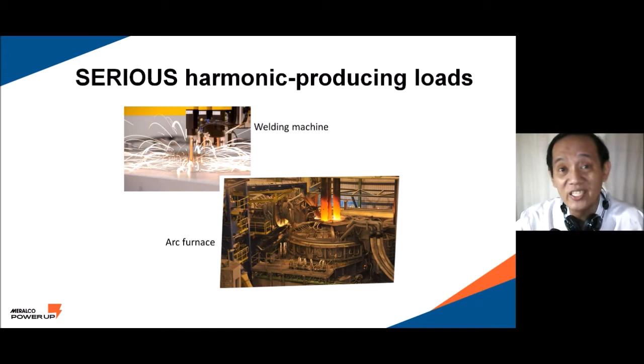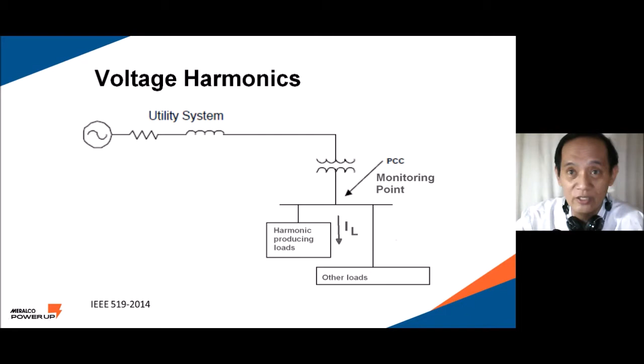When you measure harmonics in your system, you always use the point of common coupling, basically the secondary of your transformer. You don't measure harmonics at the loads because it gives very skewed data, which is not helpful when evaluating the effects of harmonics in your system.